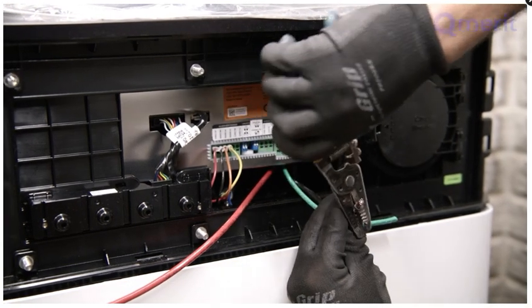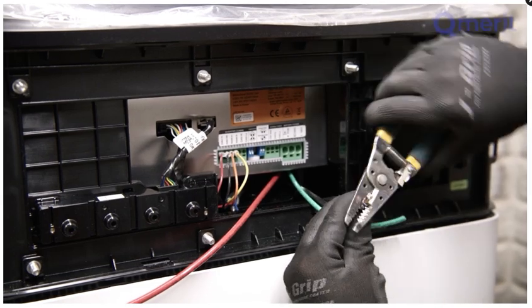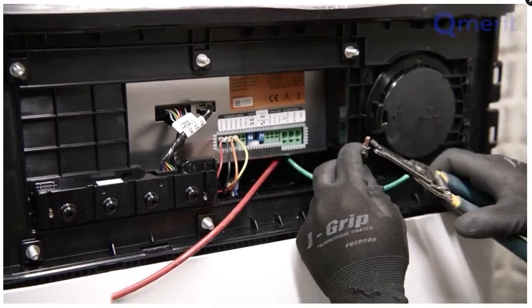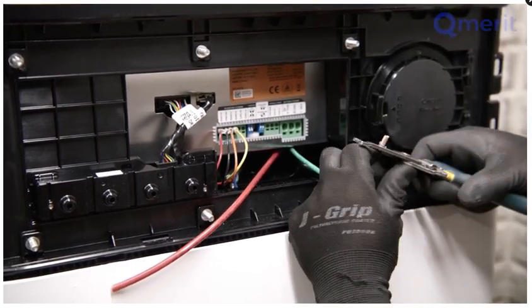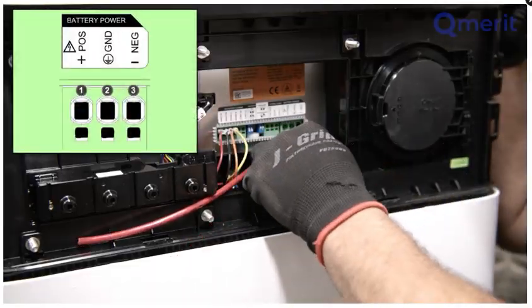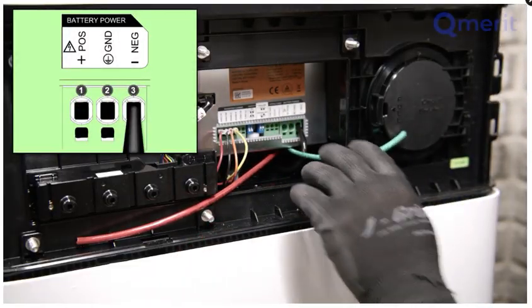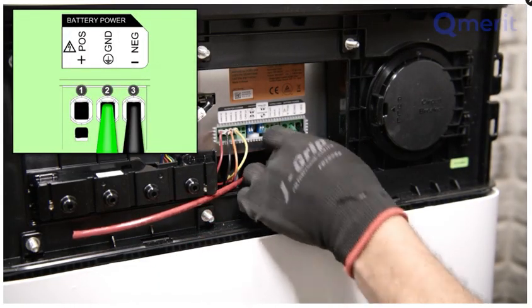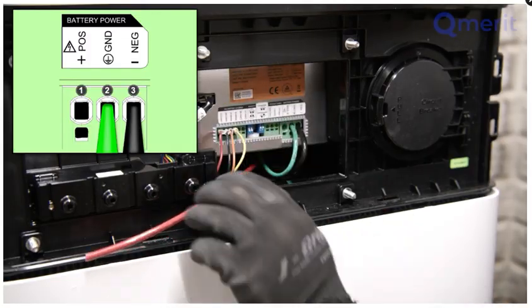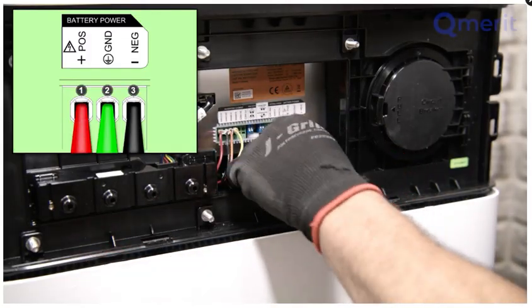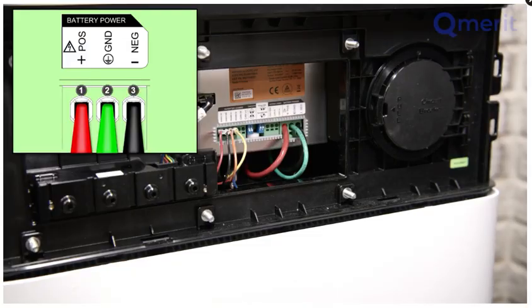Next, we install the high voltage DC. Strip the power terminal cable by 15 mm or 0.6 of an inch. Connect the negative line of the power cable to terminal 3. Connect the ground wire to terminal 2. Connect the positive line of the power cable to terminal 1.